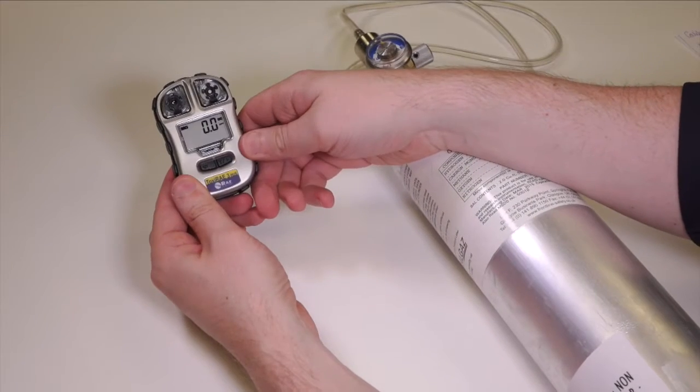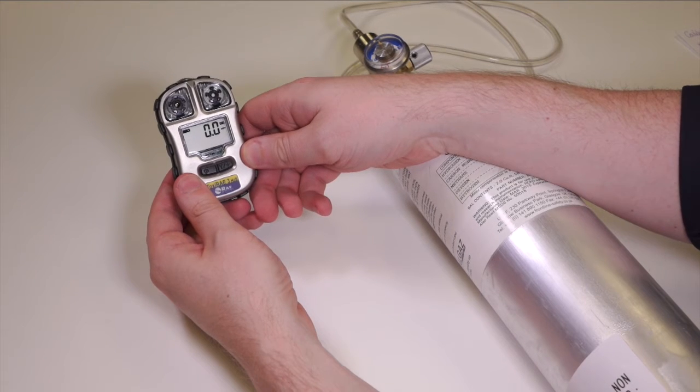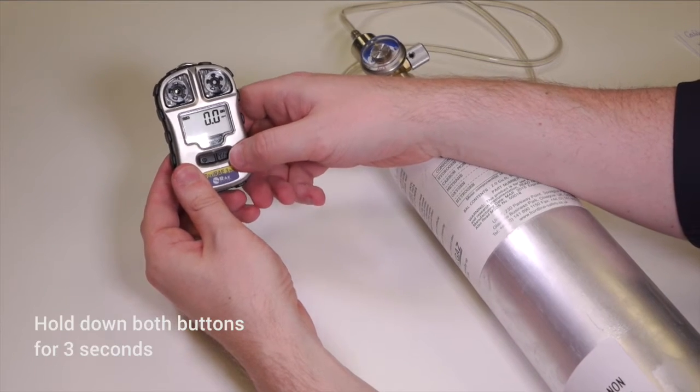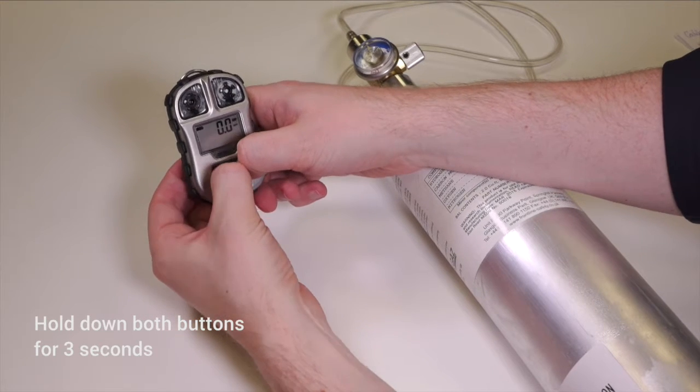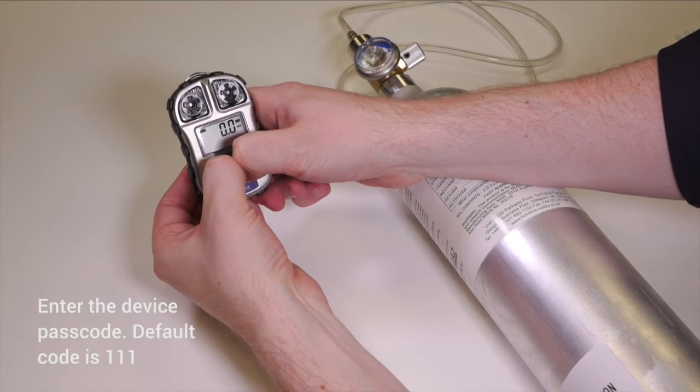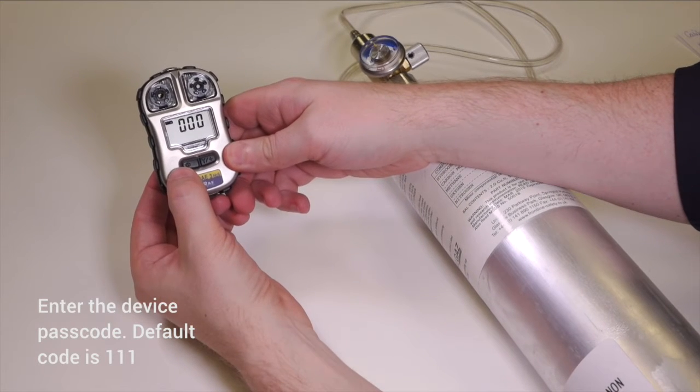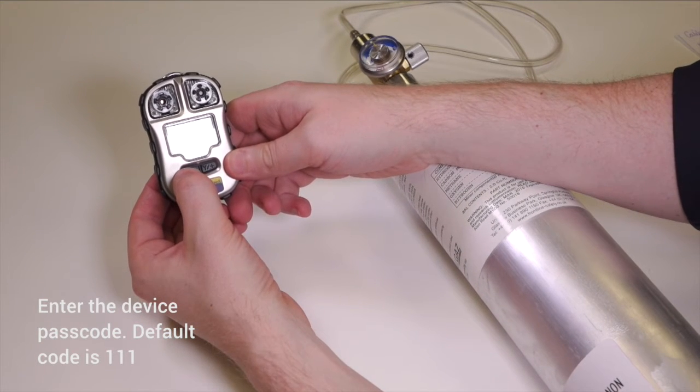To calibrate the ToxiRAE 3 H2S monitor you need to get access to the calibration menu. You do this by holding down both buttons simultaneously for around three seconds and then it'll ask us to enter a passcode. The passcode is a default setting of triple 1.